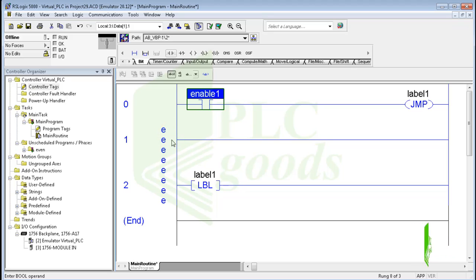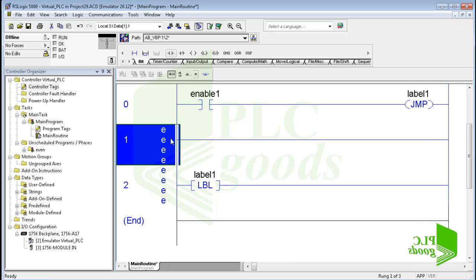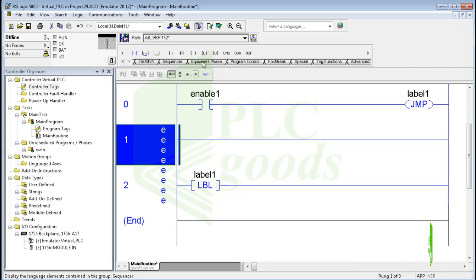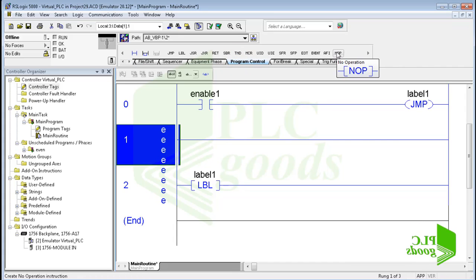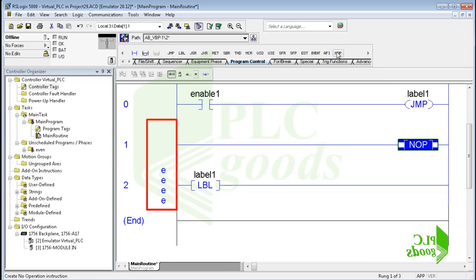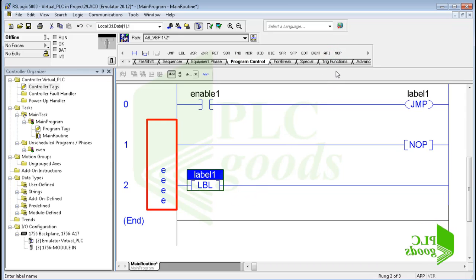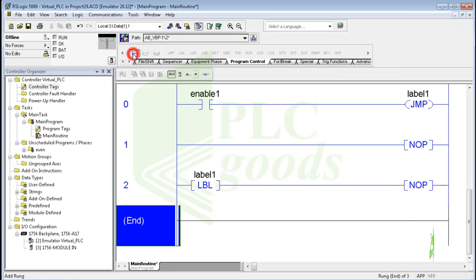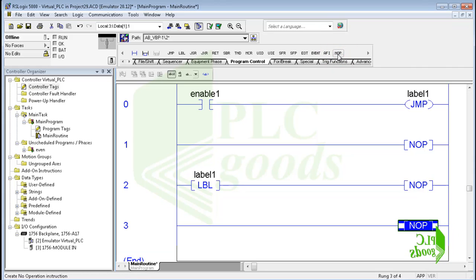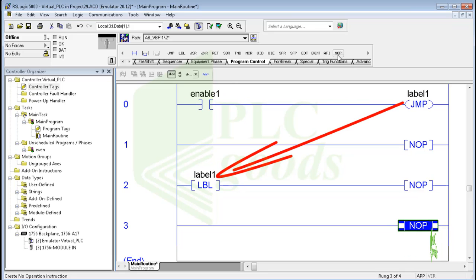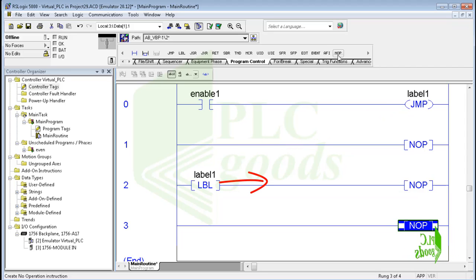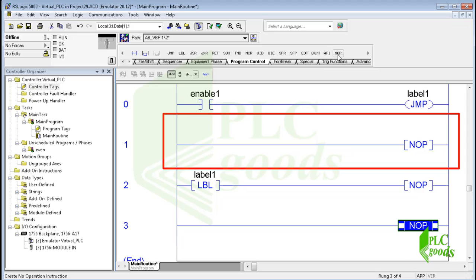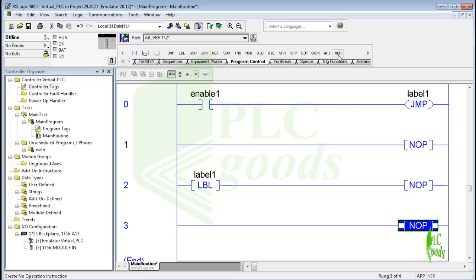Between the inserted jump and label instructions, I can add other rungs and use any instruction. I can also use the no operation instruction from the program control tab — this instruction won't do anything, but it will remove the empty rung error from my program. Based on the program, if the jump instruction is enabled by a contact, it skips to the reference label instruction and the controller continues executing from there, skipping that portion of the program.